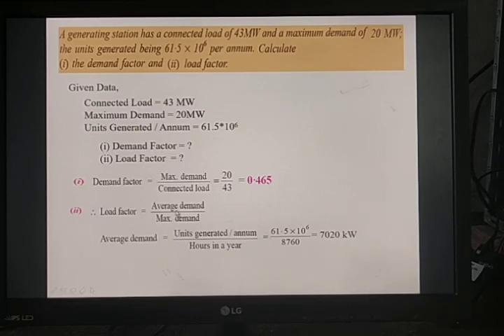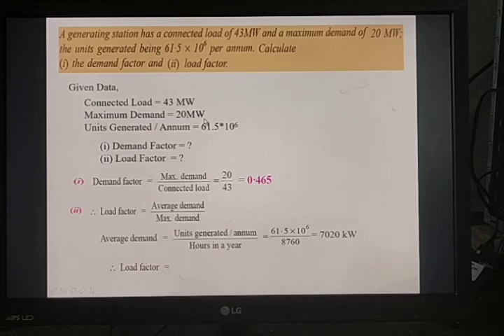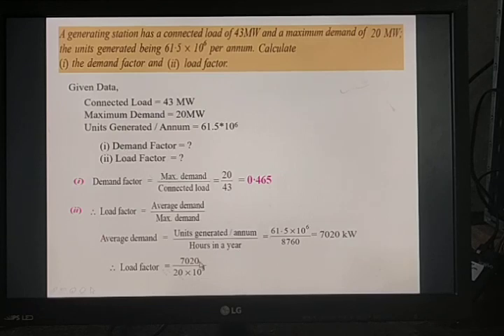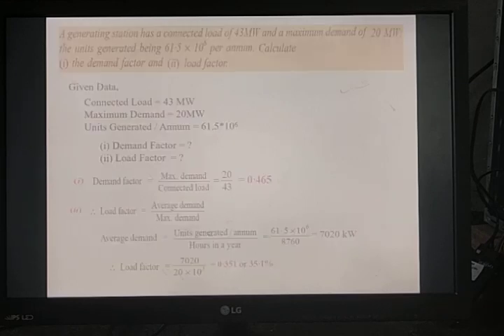Now we know the average load and maximum demand, so we can find the load factor: load factor = average load / maximum demand = 7,020 / (20 × 10³ kilowatt) = 0.351, or 35.1%. Therefore, the demand factor is 0.465 and the load factor is 35.1%.